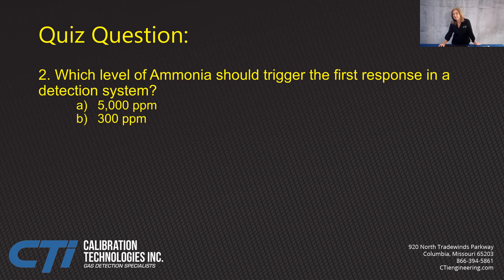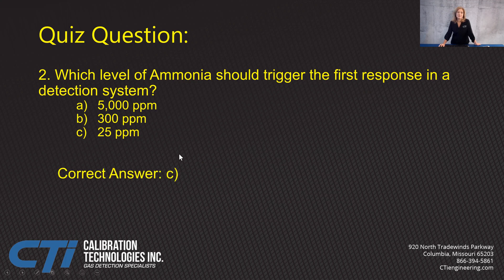Another quiz question: what level of ammonia requires a first response? Is it 5,000 ppm, 300 ppm, or 25 ppm? It's 25 ppm. Anything below 25 ppm, you don't have to signal any sort of alarm. That's the first level that IIAR notices. The correct answer is C.